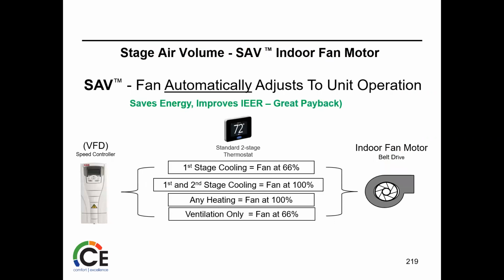So first stage cooling, fan low speed. First and second stage, you get fan at 100%. Any heat call, fan at 100%. Just ventilation, you're going to get fan at 66%, which is 40 and 60 hertz, which you've probably all run into one by now.